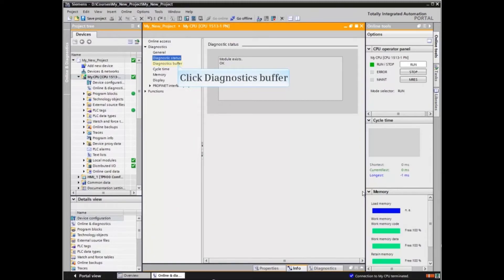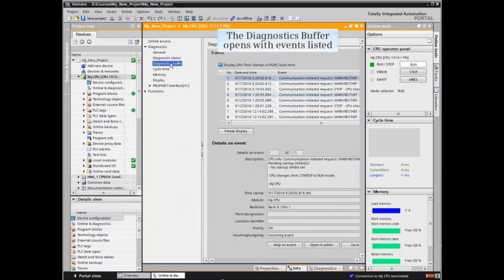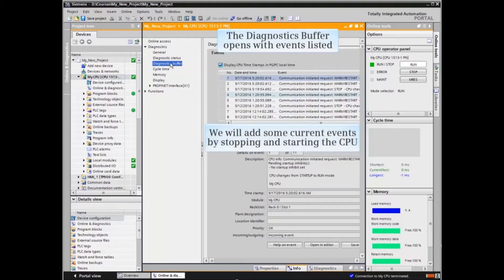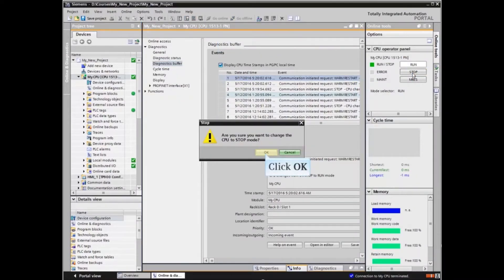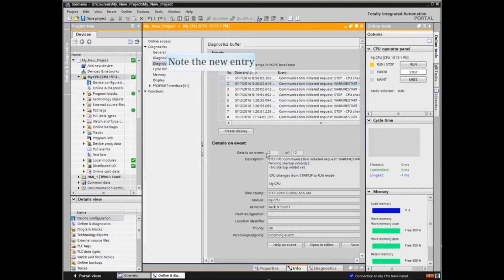Now let's take a look at the Diagnostics buffer. The Diagnostics buffer opens with several past events listed. We will add some current events by stopping and starting the CPU. Stop the CPU remotely by clicking the stop button. Note the new entry: Communication initiated request — Stop.